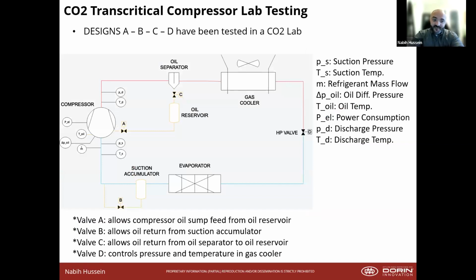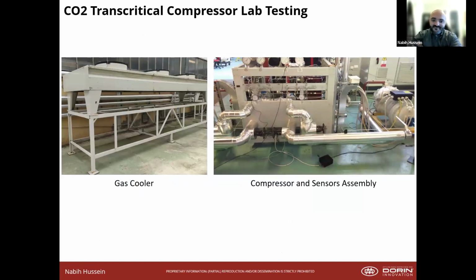This is a typical test lab setup. You have the compressor, all of these sensors, and the control valve. So whether you're trying to turn off oil supply, this is how we set up our testing lab. It's a closed circuit; it's not actually giving any cooling load, but it has a sink for that cooling load. Here it is visually. You can see the 160 horsepower compressor off to the right, with the supply power going into it and sensors all over it. The gas cooler is on the outside. The only high pressure, high temperature part of a CO2 system is the discharge between the discharge valve and the gas cooler. Everything else is low temperature, low pressure.